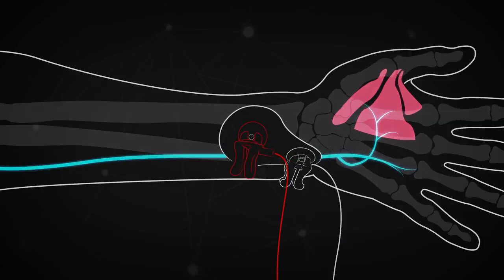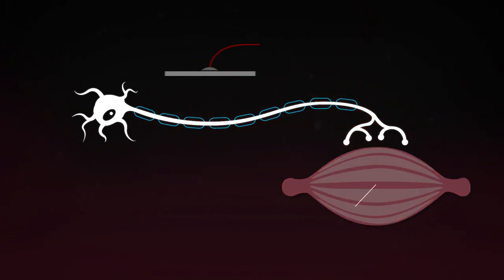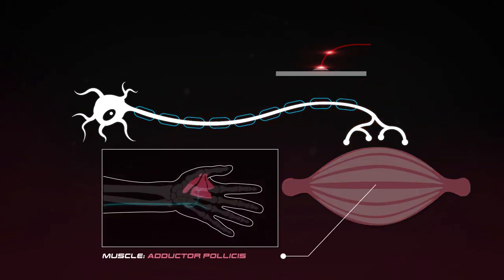Nerve stimulation versus direct muscle stimulation. Correct electrode placement is imperative in order to stimulate the target motor nerve while avoiding any direct stimulation of the target muscle, in this case the adductor pollicis.